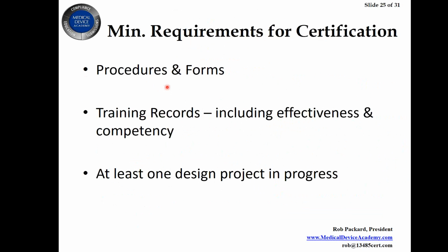And you want to have at least one design project in progress. You have to have some records. You don't have to have the DHF completed, but you have to have some records in there. So an approved design plan, maybe a design meeting, maybe you've conducted a hazard identification and had approved design inputs. That would be great. And maybe now you're playing around with some concepts and you're doing some preliminary screenings to make sure it's compatible with the sterilization process, or you're doing software development, you're doing iterative design of the different units, subunits of the software, each module of it. That'd be a great place to be as a minimum requirement.